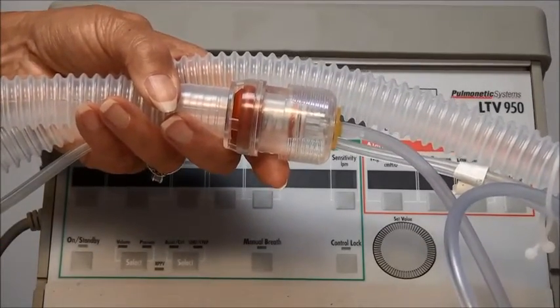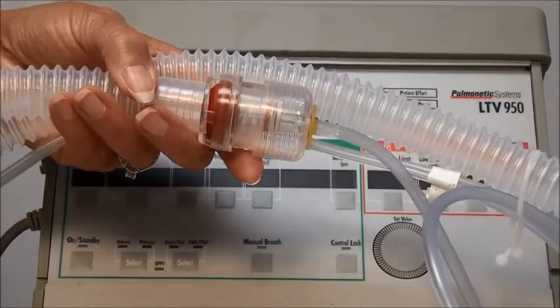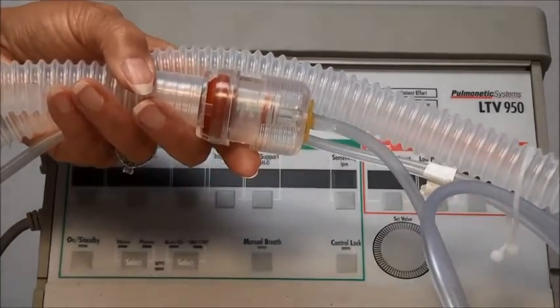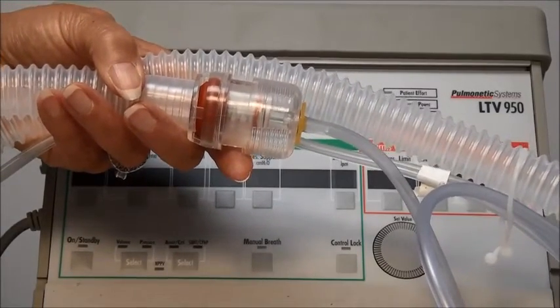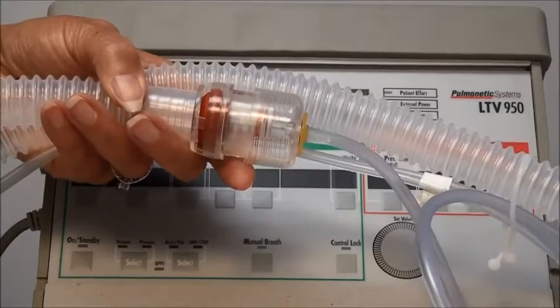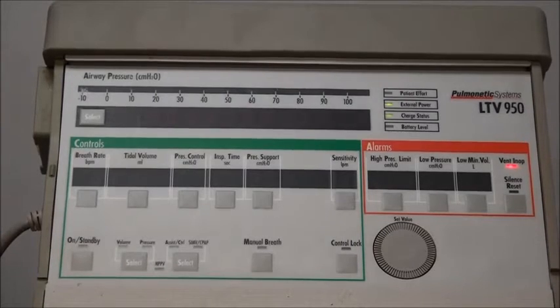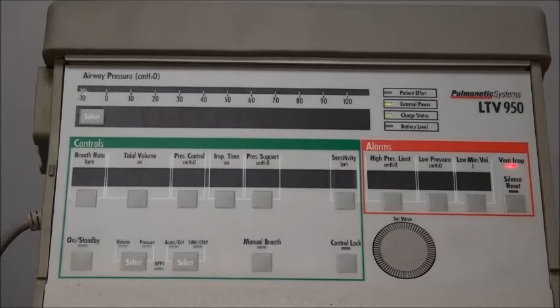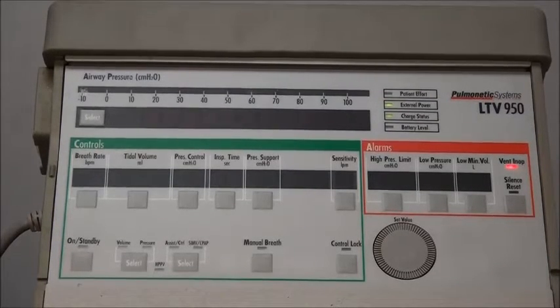And that could also be a problem actually at your patient, depending on what kind of trach tube they have in, depending on how much air or water you have in the cuff. If you don't have enough, that can also cause a low pressure alarm. Your low minute volume alarm also will go off if you have any sort of disconnect or leak in the circuit. And a lot of times with patients who are speaking and you are taking the air out of their cuff, you can get a low minute volume alarm, and sometimes that will need to be adjusted. So that is what everything is on the front of your ventilator.